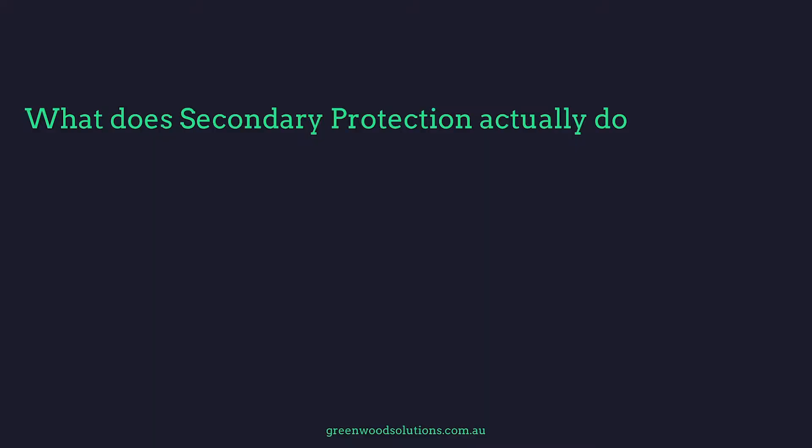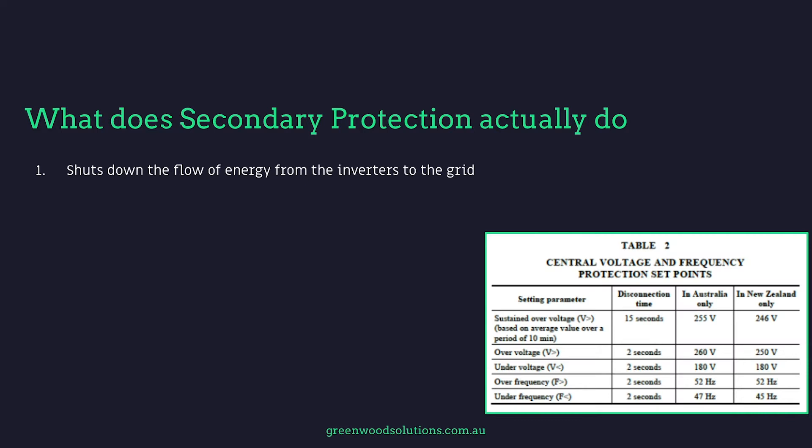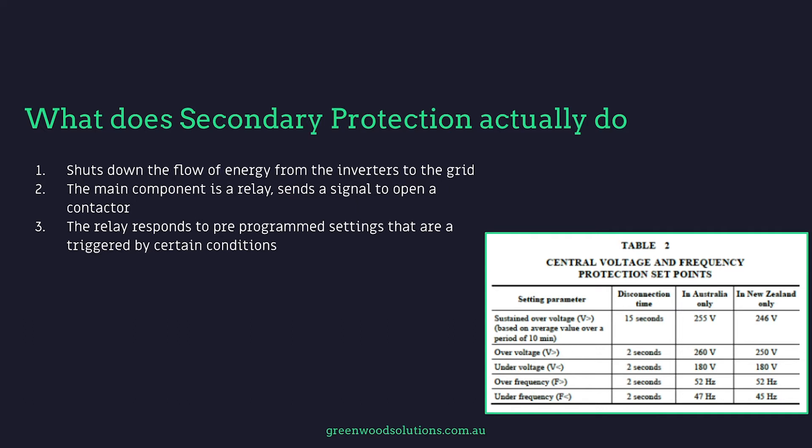So what does it actually do? Well, it shuts down the flow of energy from the inverters to the grid. The main component is a relay that sends a signal to open a contactor. The relay responds to pre-programmed settings that are triggered by certain conditions — for example, over voltage, under voltage, over frequency and under frequency.